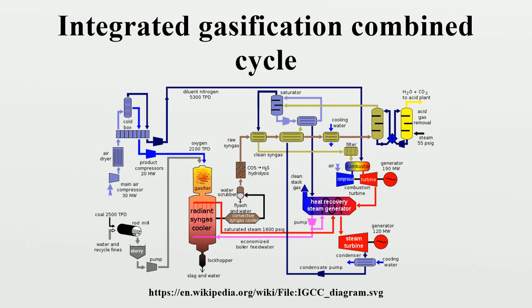There are several refinery-based IGCC plants in Europe that have demonstrated good availability after initial shakedown periods. Several factors help this performance. None of these facilities use advanced technology gas turbines. All refinery-based plants use refinery residues, rather than coal, as the feedstock. This eliminates coal handling and coal preparation equipment and its problems. Also, there is a much lower level of ash produced in the gasifier, which reduces cleanup and downtime in its gas cooling and cleaning stages.